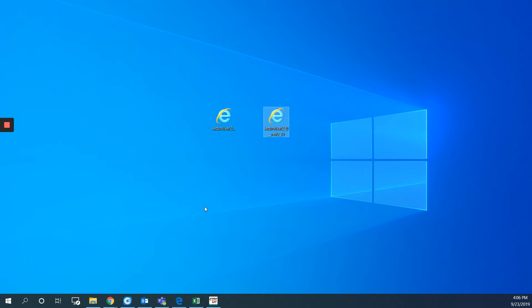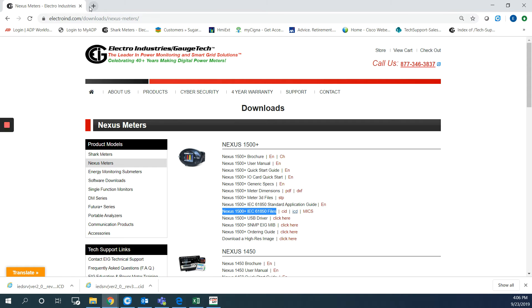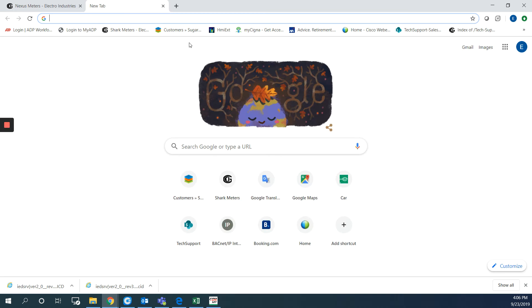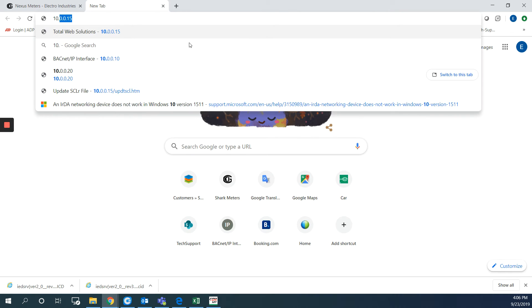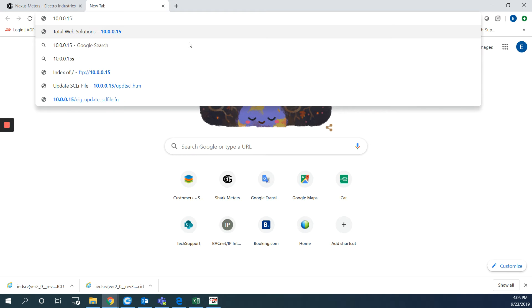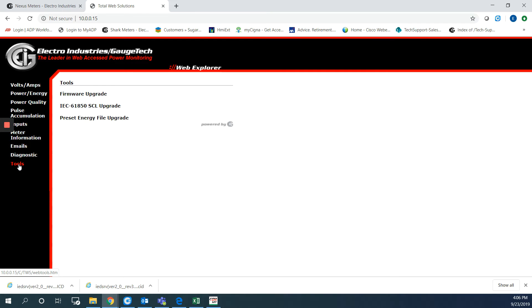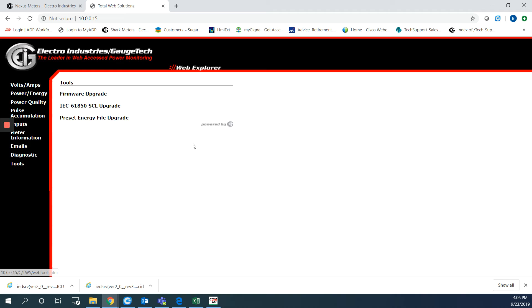To upload the file back to the meter we can do that through the web page also. So I will type the IP address of my meter which is 10.0.0.15. Then I will go to tools and hit IEC-61850 SCL upgrade.